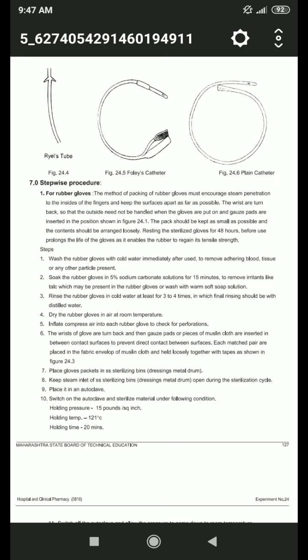Then place the gloves packed in the SS sterilizing bin, that is the dressing metal drum. Keep the steam inlet of the SS sterilizing bin open during the sterilization cycle. Then place it in the autoclave. Then switch on the autoclave and sterilize the material under the following conditions. Holding pressure is 15 pounds per square inch, holding temperature is 121 degrees Celsius, and holding time is 20 minutes.